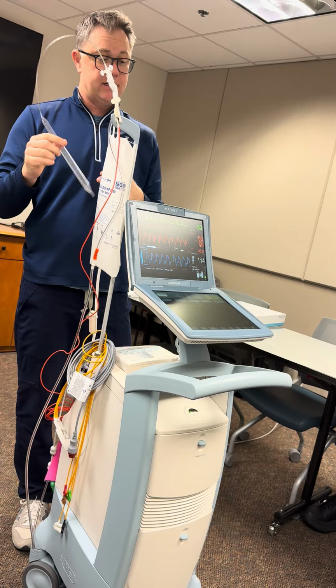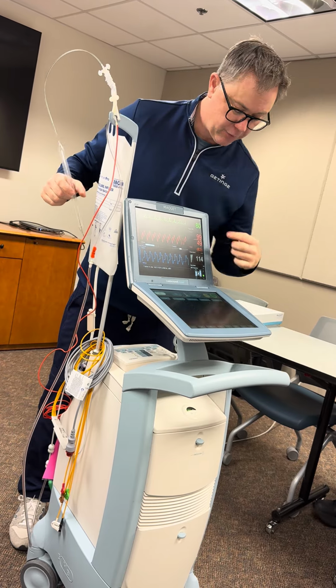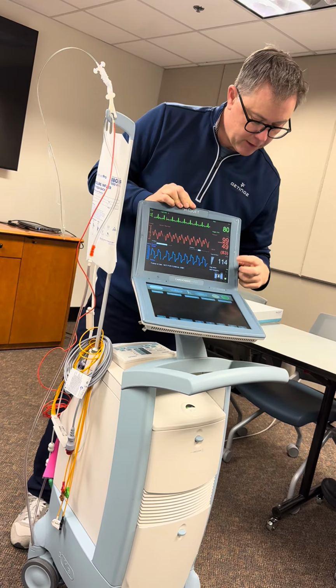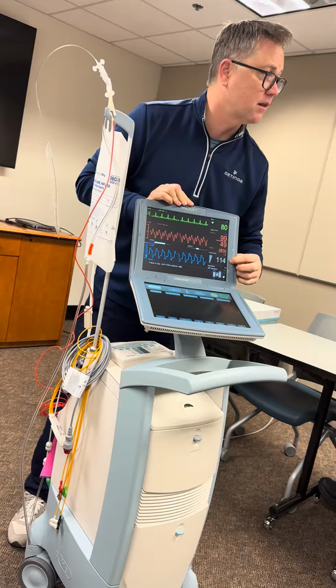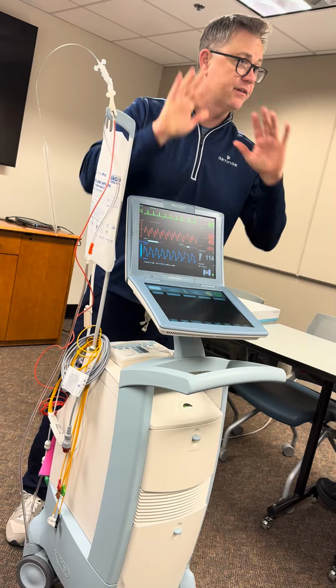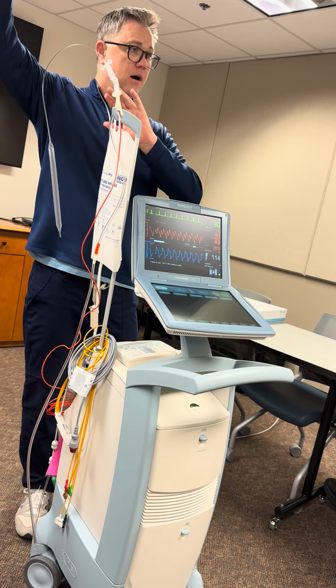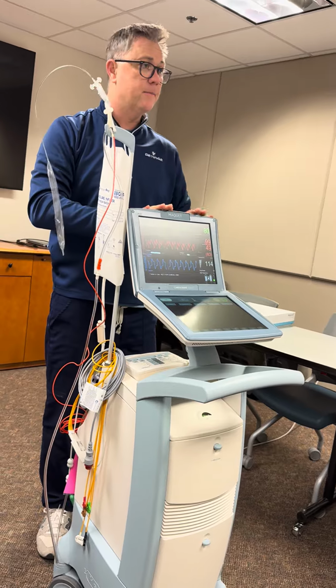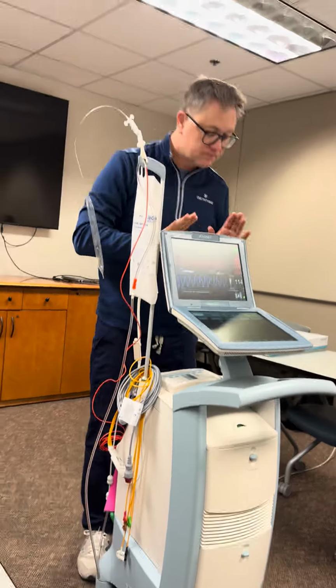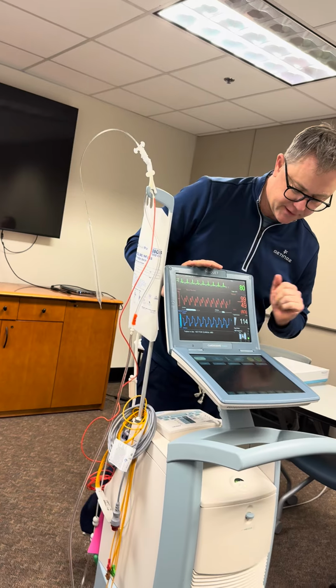Philips monitor doesn't know that. It's looking for the highest peak on the waveform, so a lot of times the Philips monitor is going to call this number the systolic number in your room. So just be aware of that. If there's ever any discrepancies on what's on the screen and what's on the balloon pump, these are the most accurate numbers. Titrate your drips, everything off of this machine.